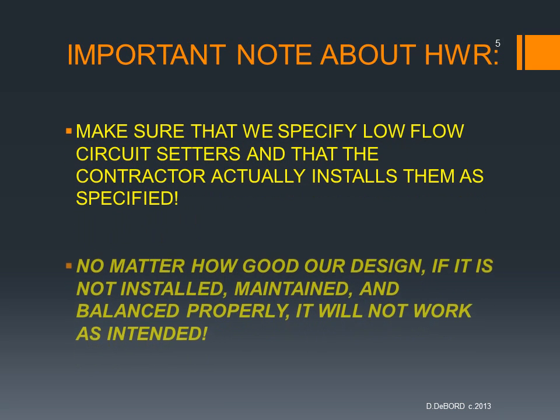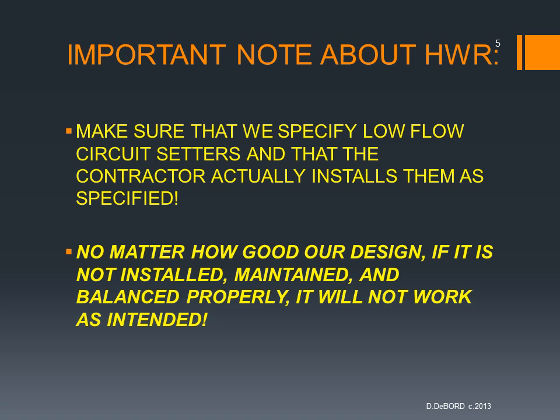Make sure that we specify low flow circuit setters, because they're more sensitive and they work better, and that the contractor actually installs them as specified. No matter how good our design is, if it is not installed properly and maintained and properly balanced, we can't expect it to work as intended.